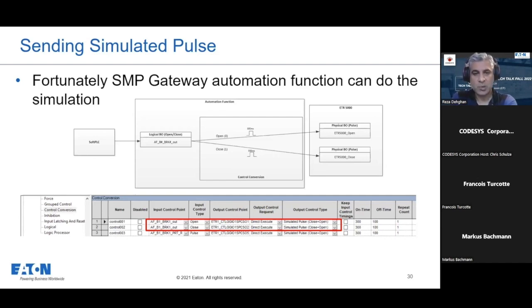The input control point is the point that SoftPLC generates. And then we can say, okay, if you want to execute or to use this as an open or close, and what kind of command, it would be a simulated command. And under on time and off time, we just specify the shape of the pulse. So when we say the on time, basically your pulse command would be up for 300 milliseconds. Next page.